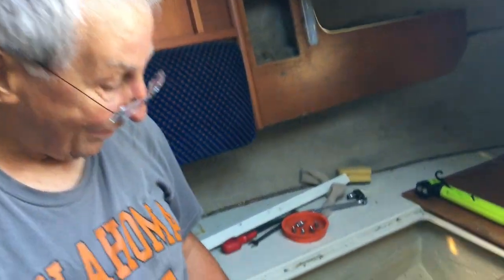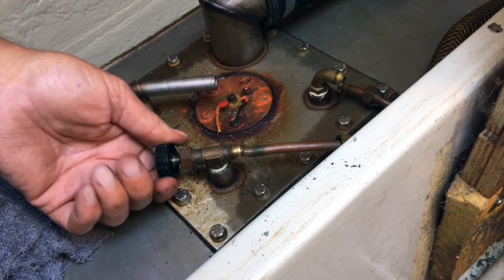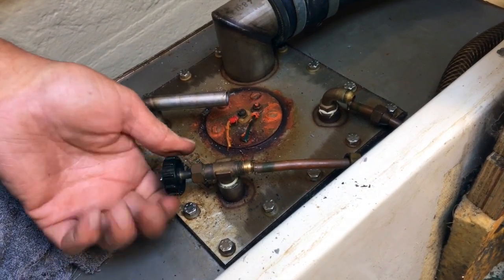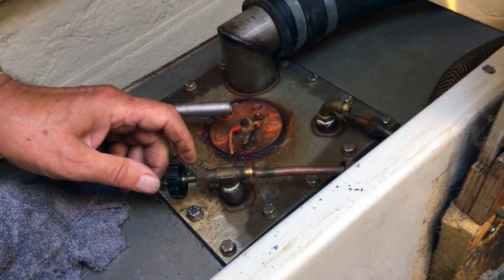There's the fuel shut-off valve there on the top of the tank. At the moment it shuts - righty tighty and it's tight. This has been taught to me many years ago, 58 years ago when I started as an apprentice. You open the valve fully, and then when you get to the end you close it half a turn so the next person that comes to it - when they grab hold of it it's loose, so they know it's open. If it's closed, it's tight. If you leave it tight in the open position, they don't know whether it's open or closed, so sometimes they'll turn it left to open it and they'll break it. Just a little thing taught to me as an apprentice many years ago.